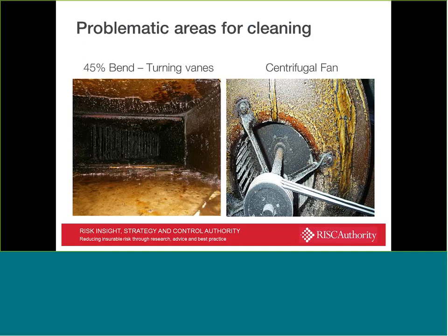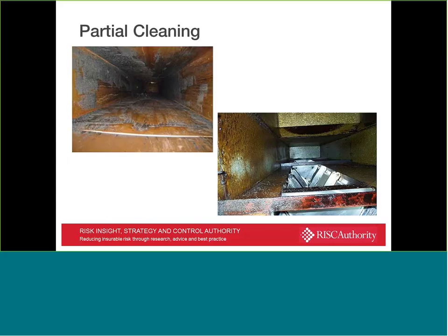So when it comes down to design, it's important to ensure we try to minimise certainly the 45 degree or even the 90 degree bends in the systems. Shallower bends, or alternatively having radial bends, are a far better approach. In circumstances such as this, you're clearly going to need to ensure that both the vanes, the fan blades, of the fans can all be cleaned effectively every time the internal cleanliness of the system is being checked and cleaned. Partial cleaning is a problem and happens quite commonly.